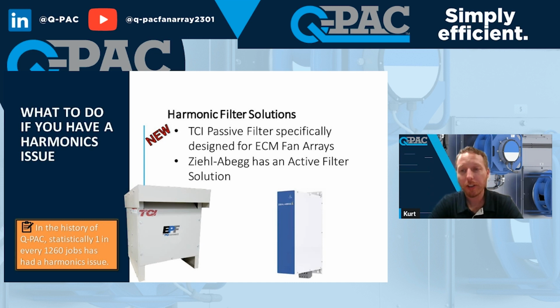TCI specifically, all they do is make a bunch of devices, and a bunch of them are for harmonics. They have a calculator that you can go onto their website for, and they have this brand new passive filter specifically designed for ECM fan arrays. If your fan array has Ziehl-Abegg fans, Ziehl-Abegg also has a solution, and we will connect you with them so you can figure out exactly what you need. So, any other questions around harmonics, Eddie?